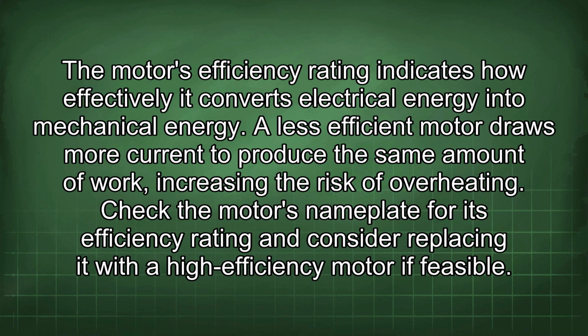The motor's efficiency rating indicates how effectively it converts electrical energy into mechanical energy. A less efficient motor draws more current to produce the same amount of work, increasing the risk of overheating. Check the motor's nameplate for its efficiency rating and consider replacing it with a high-efficiency motor if feasible.